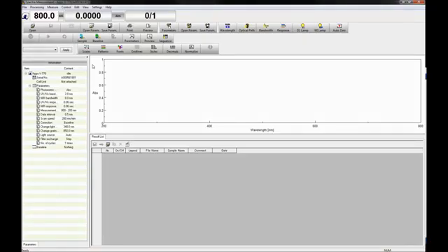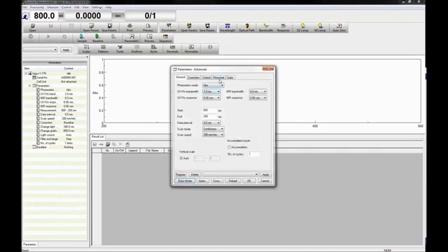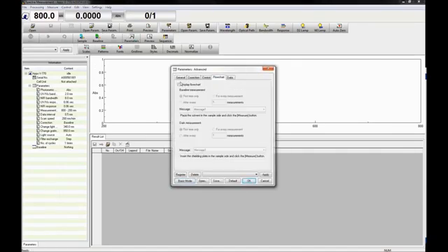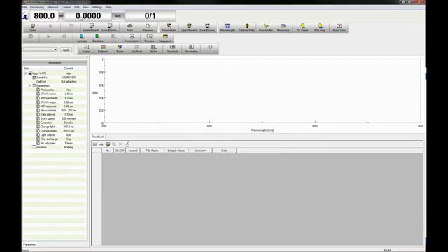Sequential measurements on multiple samples can be carried out, each of which can be assigned different measurement parameters, sample name, comment, and file name. Baseline measurements can also be included in the sequence. Make sure that display flowchart is not selected in the parameters tab, and either select measure, sequence measurement, or choose the sequence icon in the menu toolbar.